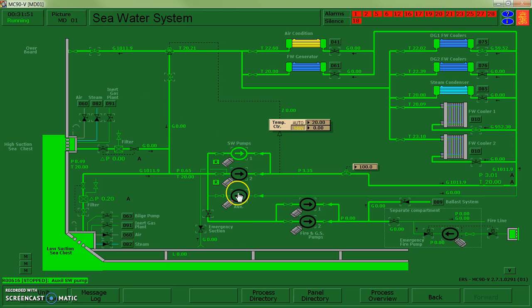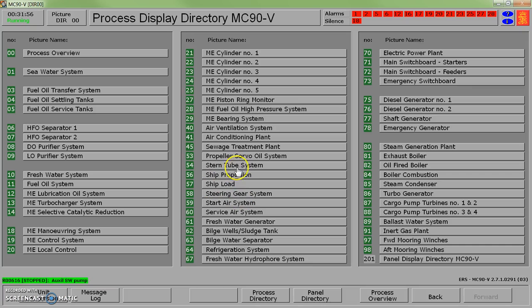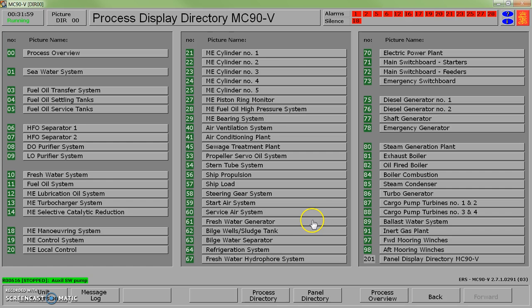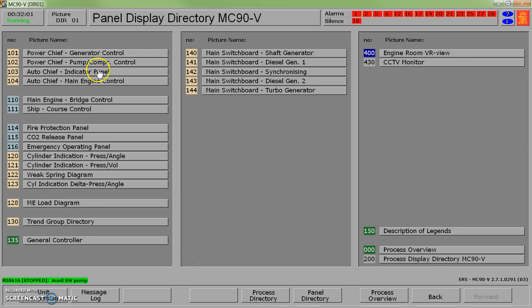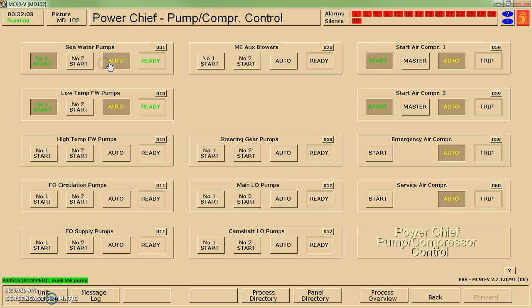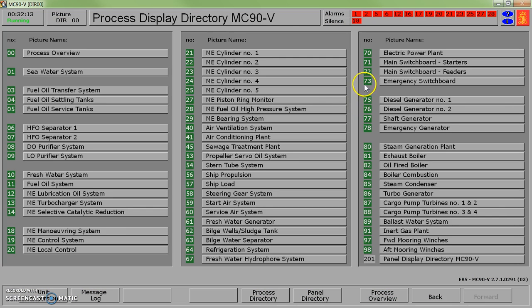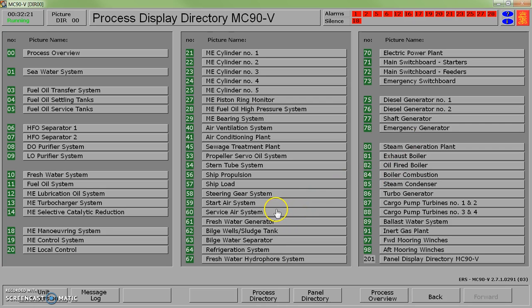Auxiliary isn't required. I still have cooling water system, start air system looks okay. The other thing that I want to make sure is that since I'm relying pretty heavily on my auto controls, that they are in fact still functioning, and it looks like they are. So I think at this point I have some pretty stable auxiliary systems in place. I have electrical supply, I have air supply, my controls should be functioning.